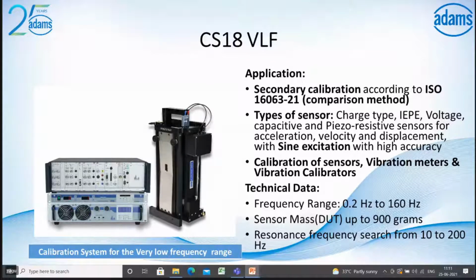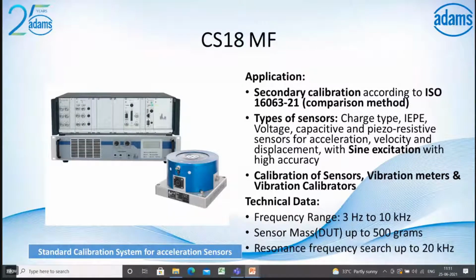And the CS18MF. Only the frequency ranges and the excitation differ. That was the very low frequency shaker; here it is the medium electrodynamic shaker. This is also a secondary calibration according to ISO standard 16063, and you can calibrate by the comparison method. The types of sensors it supports are the same as the low frequency systems. And apart from sensor calibration, you can calibrate vibration meters and calibrators from 3 Hz to 10 kilohertz.